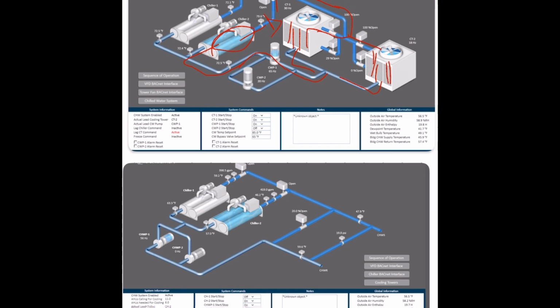Okay, now these fans over here are gonna be running, and those are gonna be running according to the demand of the system. So they can be at 30%, 20%, 100%, depending on the demand of the system. And they help to cool down the condenser water. We got two supply valves to the cooling towers, two bypasses on the cooling towers, and a supply valve on the supply from the chiller. You also have sensors that are gonna sense the temperature, water temperature, the return and the leaving temperature from your chiller and your cooling tower.